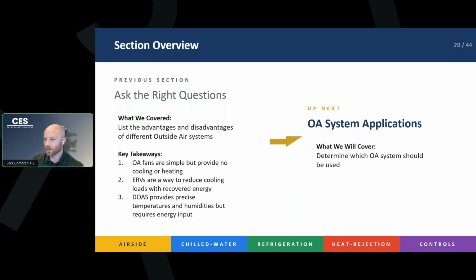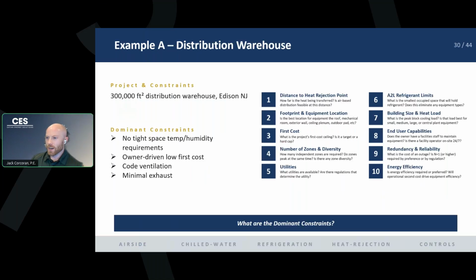All right, so we just looked at some advantages and disadvantages. So let's do some examples. Example A, right? So a warehouse, it's 300,000 square feet and it's in Edison, New Jersey. We are not looking to have a super tight temperature and humidity. As we said, it's a warehouse. It's not an office. You can let that temperature of the warehouse drift up in the summer and you can let it drop lower in the winter. The owner does not want to spend a lot of money on the HVAC. They just need the code minimum ventilation, right?